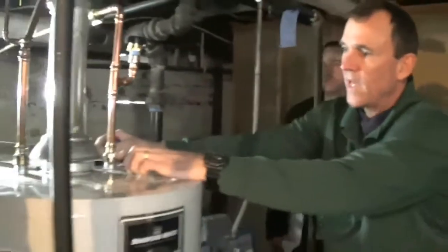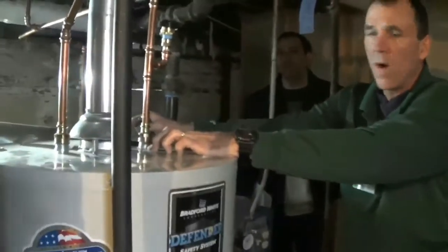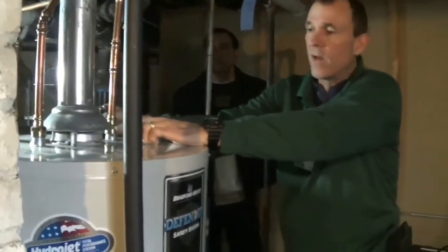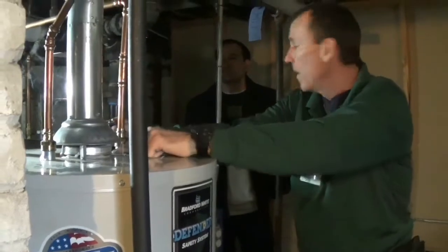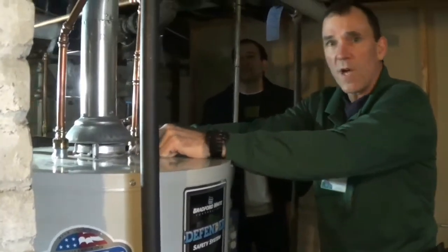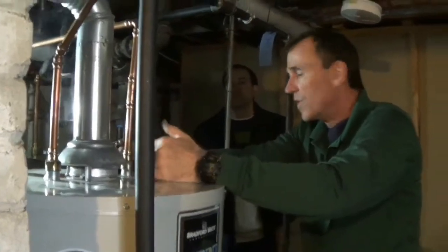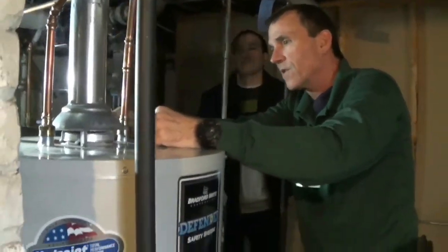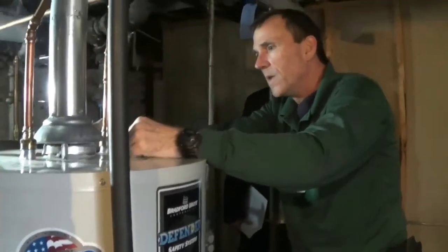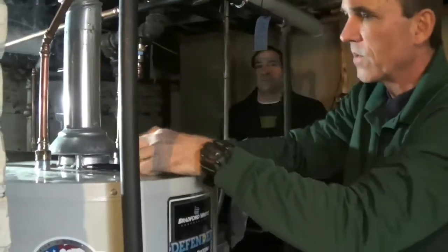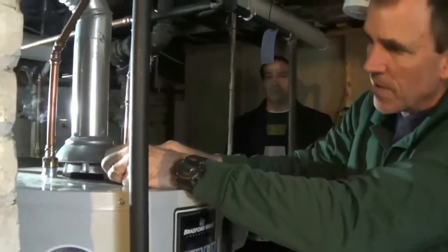Sometimes you'll have tanks that have the cold and hot water color indicator rings, the rubber rings up here, and they'll be melted because the spillage is constant here. It melts that stuff because there's exhaust pushing out and melting it. And it's been pretty close to 60 seconds, and especially on the back side.